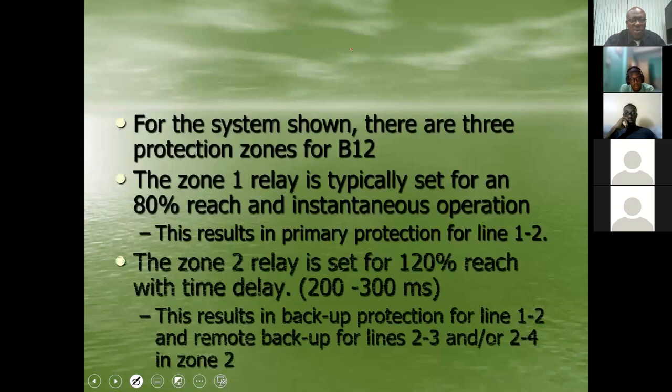So in terms of their operations, for your zone 1 setting, it is usually 80% reach, and it carries an instantaneous operation. In JPSCO, they use 90%.